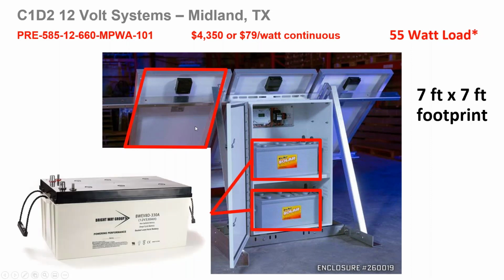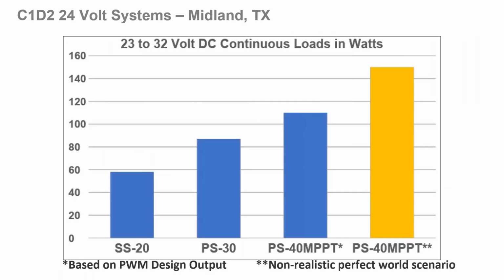Moving to the third system, to support these higher loads we have to do a couple tweaks but overall keep the same form factor. We're going to change these 180 watt modules out for 195 watt modules to give us a larger array, and we're going to switch out these 265 amp hour capacity batteries with 330 amp hour capacity AGMs in order to make the design criteria work per those ALR and battery autonomy requirements we set for ourselves.